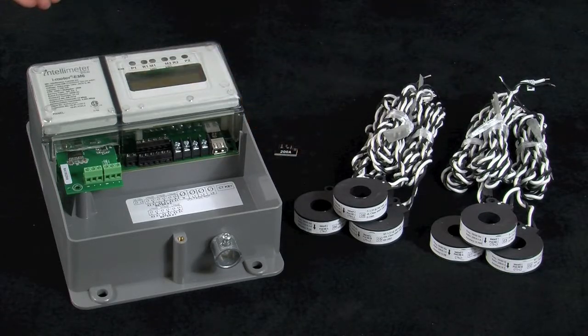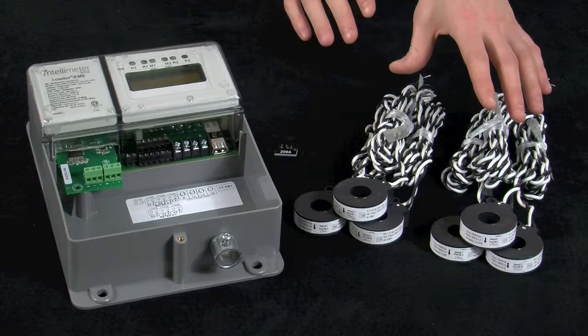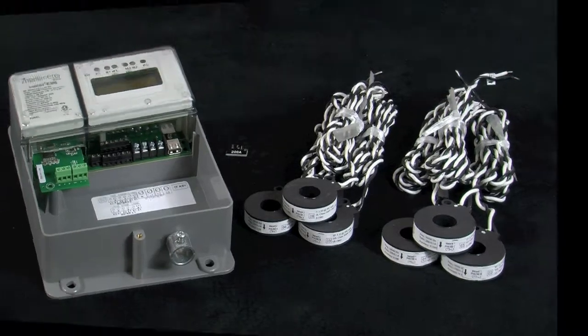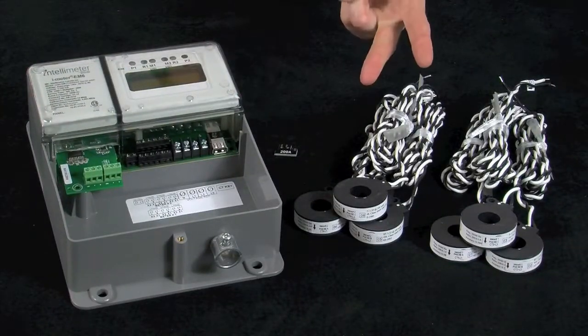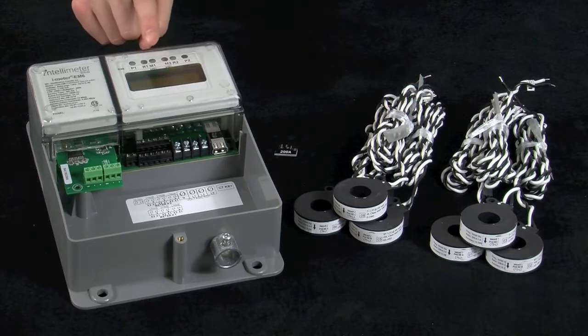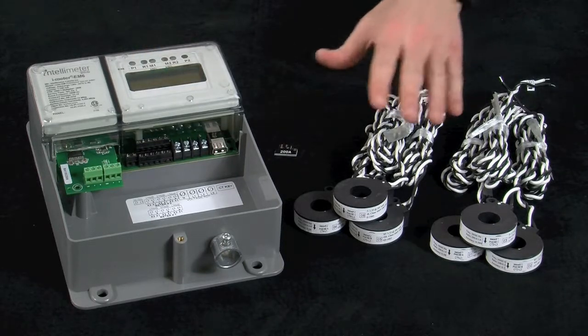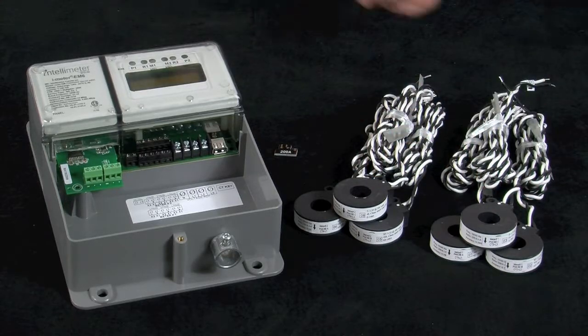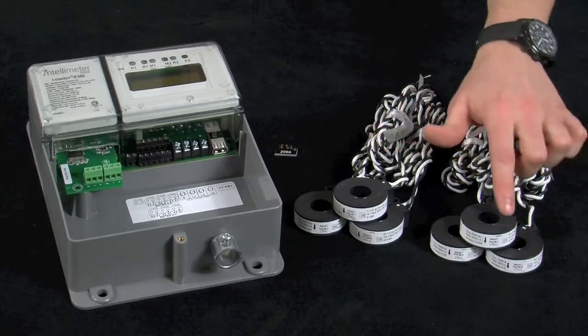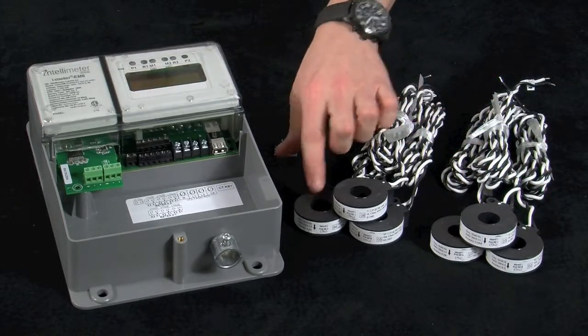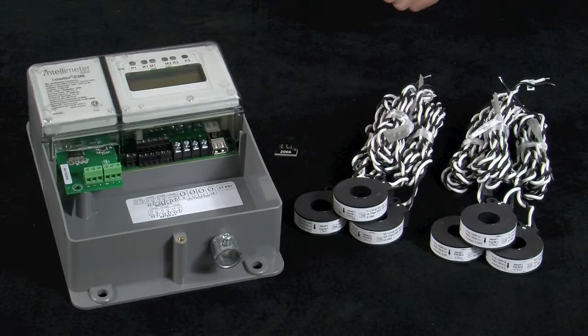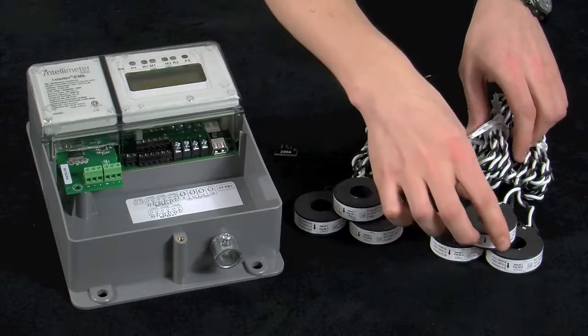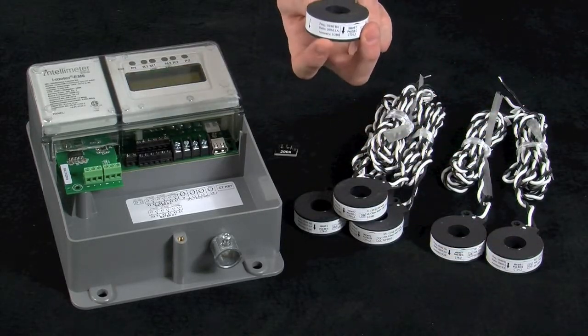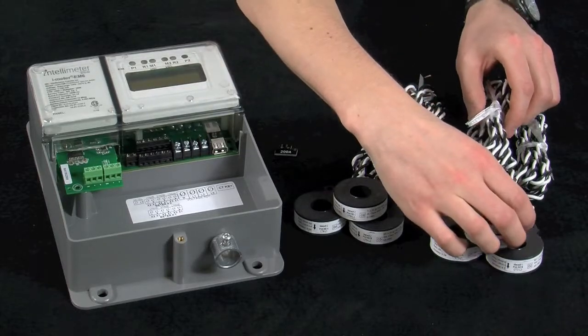So now that we've identified all of the components, let's discuss some of the CT properties in relation to the iMeter EM6. The iMeter EM6 is capable of single-phase, 2-phase, and 3-phase metering for up to 2 metering points. That being said, each CT is designated for a certain meter number and phase. CTs 1, 2, and 3 are for meter 1 and are for phases A, B, and C respectively. CTs 4, 5, and 6 are for meter 2 and are for phases A, B, and C respectively. Note that there is also a load direction arrow on the CT itself. This arrow must point in the same direction as current flow.